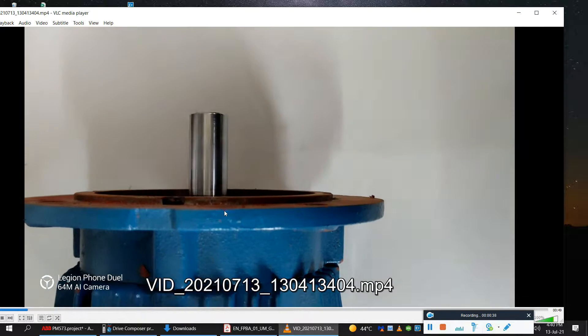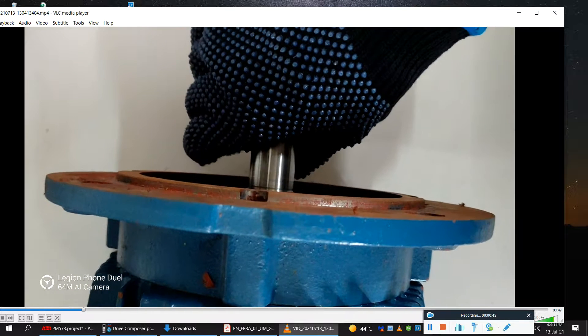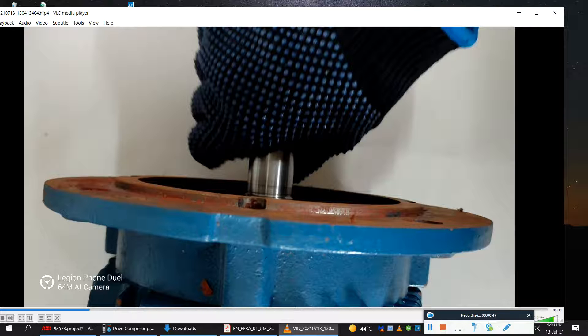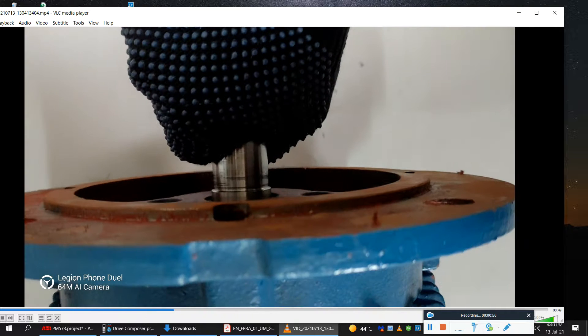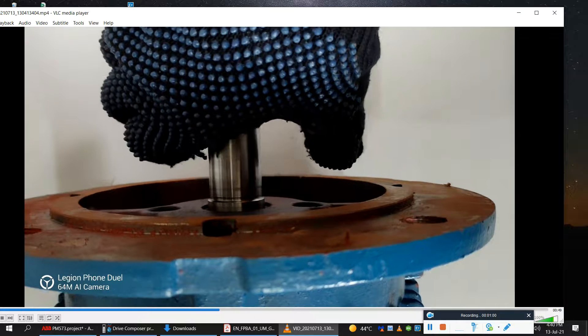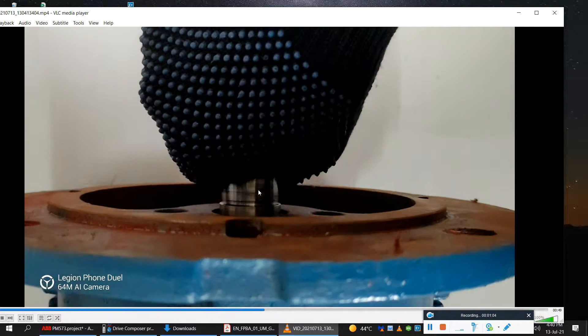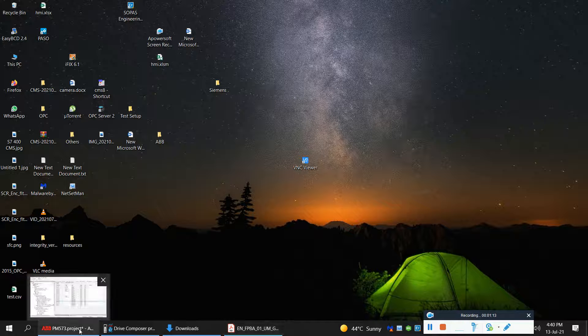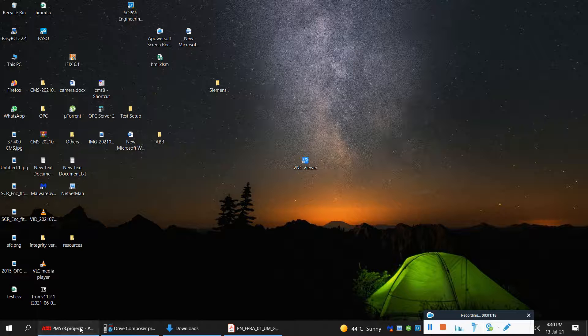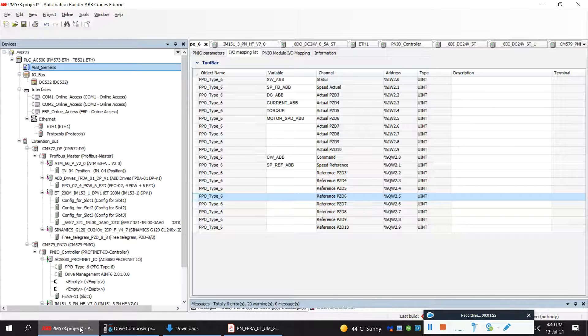This is the motor running at full RPM — a three kilowatt motor running at 1400 RPM. I stopped the motor rotation using my gloved hand. By applying some force with my hands I could stop the rotation. This is exactly the topic for today: torque control. I kept the drive in torque control mode and set eight percent as my torque reference. This means the motor will only rotate up to eight percent torque — after that the motor will stand still.